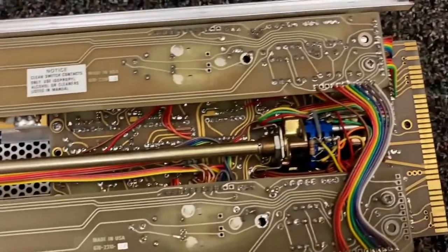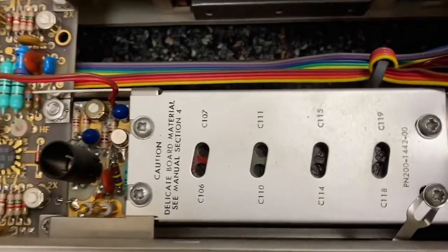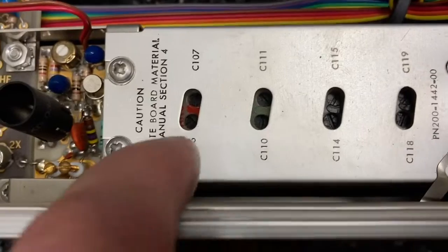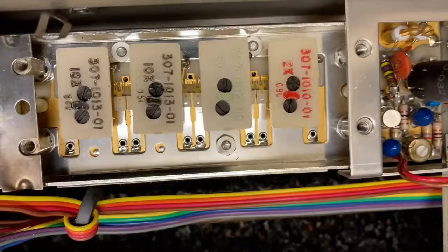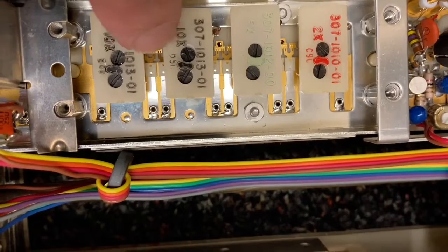Here I have a dual trace amplifier, but it's a different model than the one we looked at previously. This is like what we saw before - big long switch going all the way back here. There's a note: 'Caution - delicate board material - see manual section 4.' So there's some stuff in here that you would calibrate, and it's delicate. And under that can that said delicate material, it's a bunch of these little trim somethings.